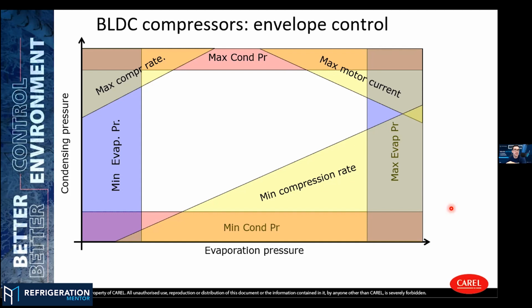Because if you're getting up into the red zone at the top, the maximum condensing pressure, and that condenser is super dirty, super plugged, you need to clean it. It can only do so much until it's going to trip off on high discharge pressure, high discharge temperature, or discharge line temperature. And same with going into the minimum evaporator, just like Marcel said, you start to get a frozen coil. And if it's a frozen coil, you have to go in and thaw that out. It's not going to fix those problems.